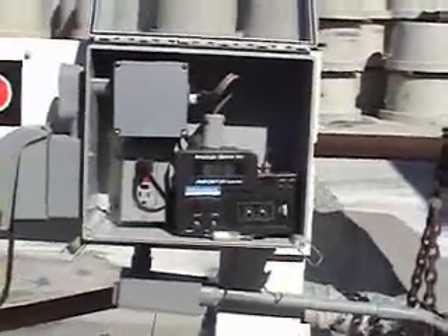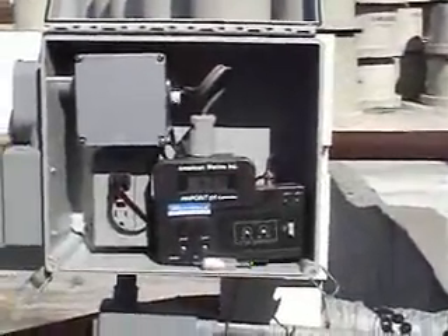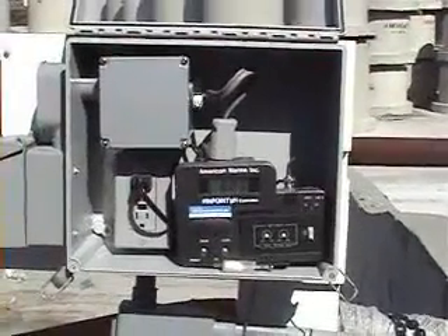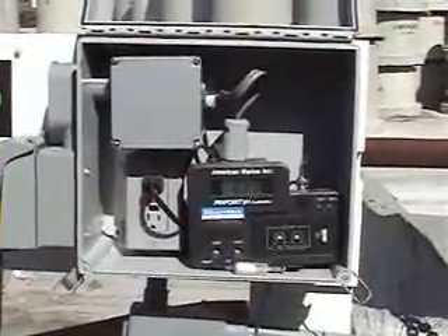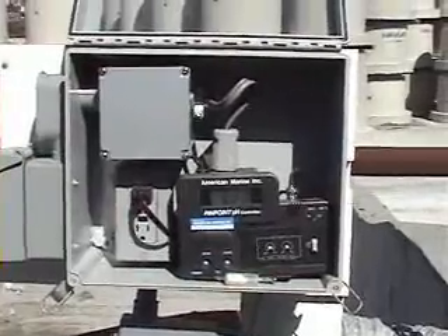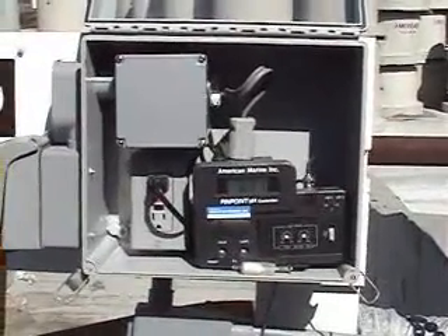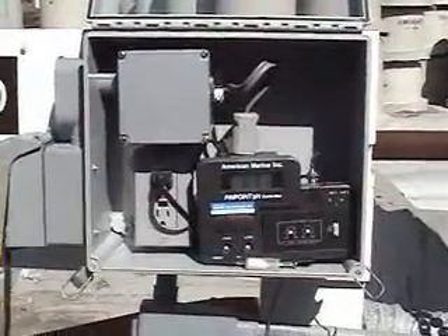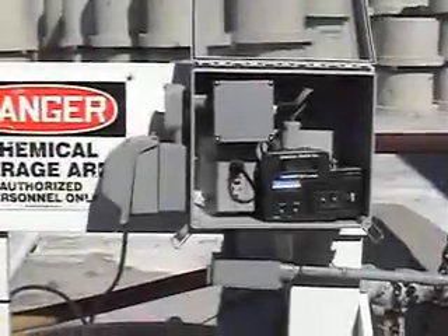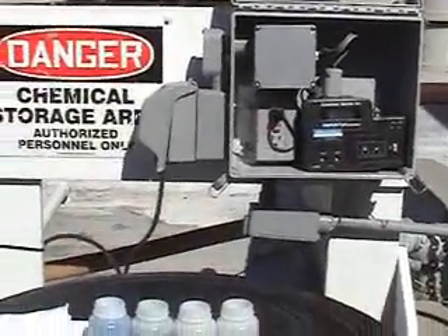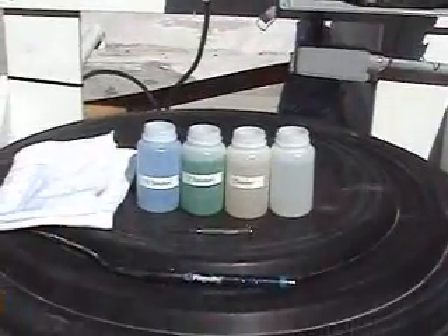Now, since we've already run through a treatment cycle and we have an acceptable pH right now, I'm going to remove the probe from the pit and perform a calibration, and in addition to the calibration, you will see how the system actually turns on and turns off. Okay, now we're going to go ahead and perform a calibration of the pH system.